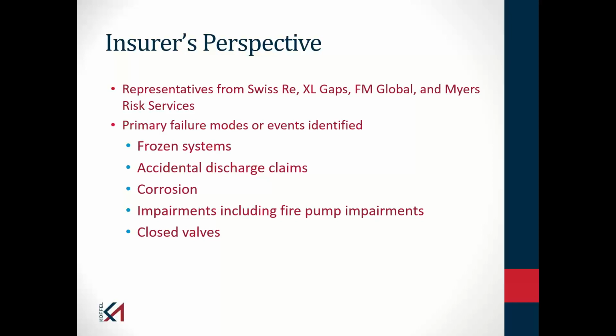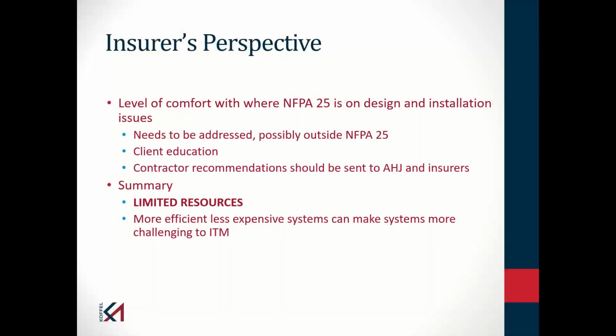But that issue's far more common than it should be, especially with that monthly inspection activity. Again, many of you have a contractor that may come in and do certain inspection, test, and maintenance activities. You most likely do not have the contractor coming in on a monthly basis. So there's an inspection activity that somebody else needs to be performing. And on larger campuses, a lot of times there's a fire marshal or safety department or somebody that would be doing that. Don't necessarily think that the insurance carrier is going to be coming in there, certainly not on a monthly basis, checking that valve.